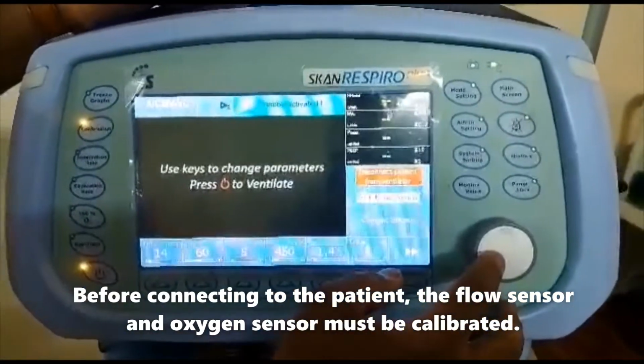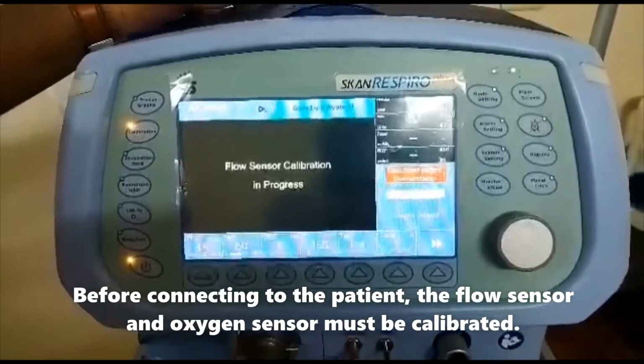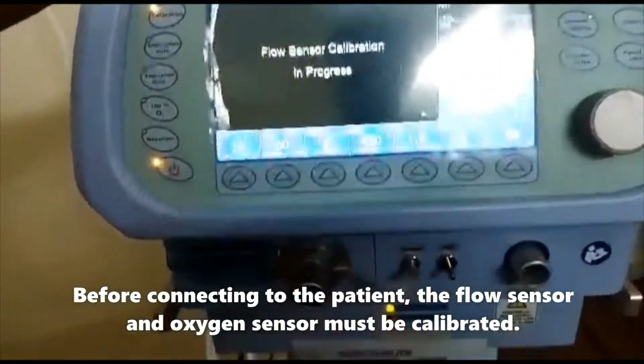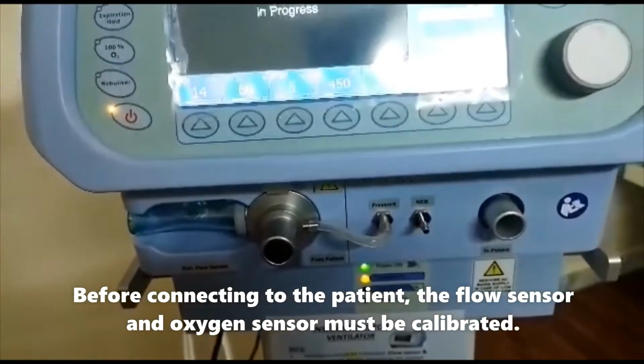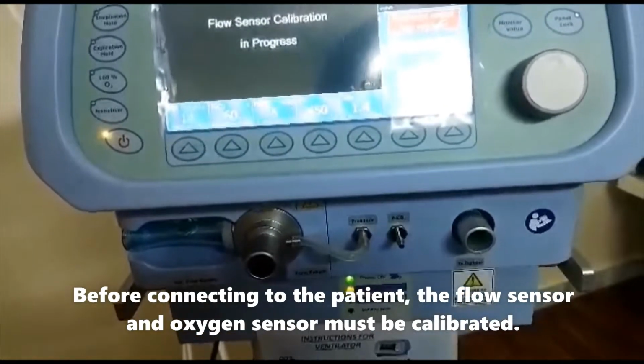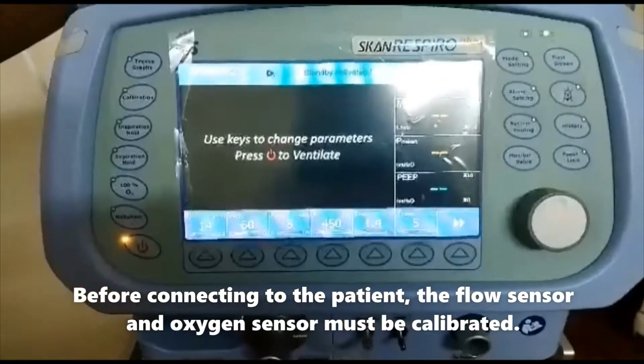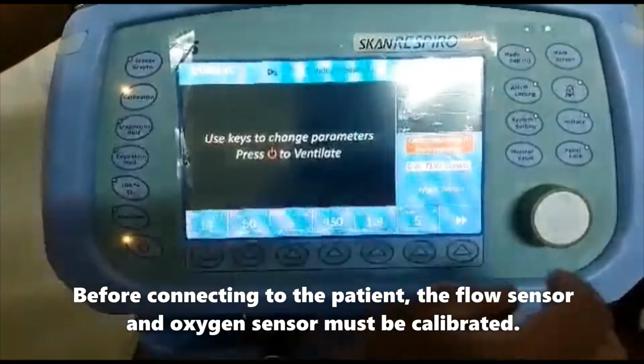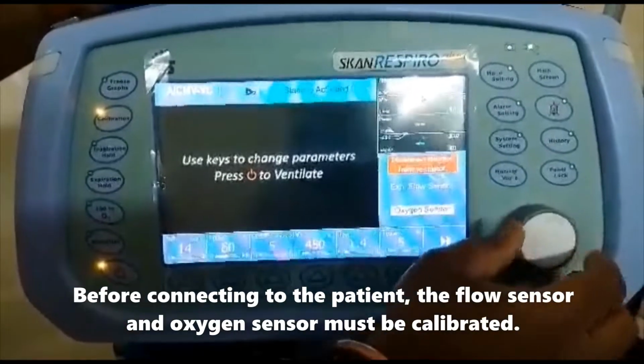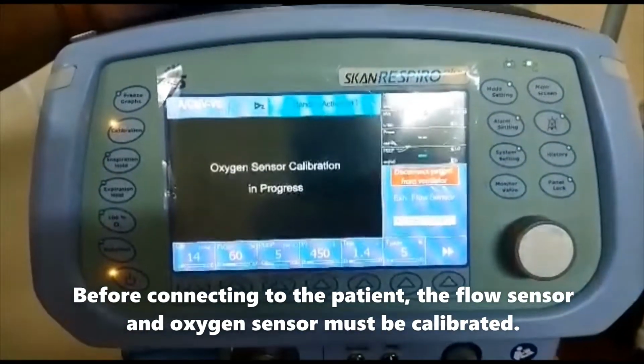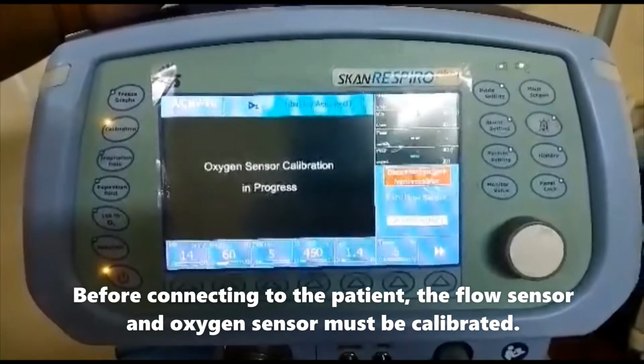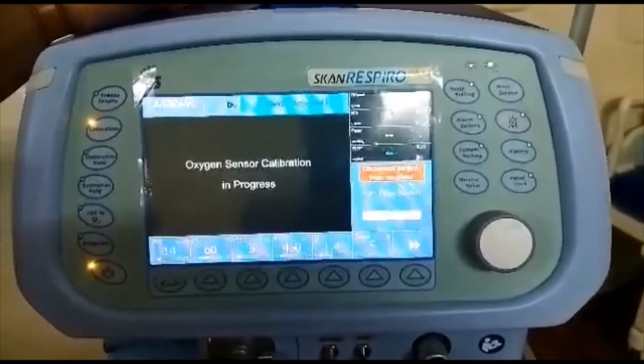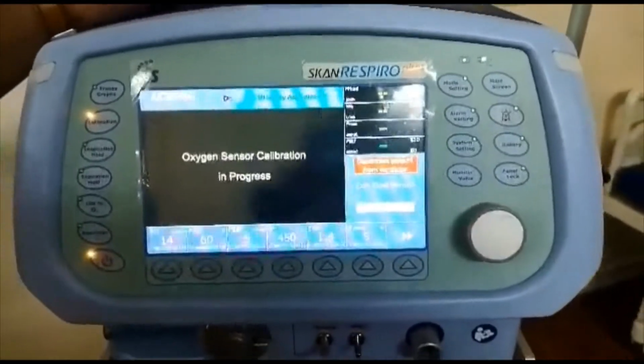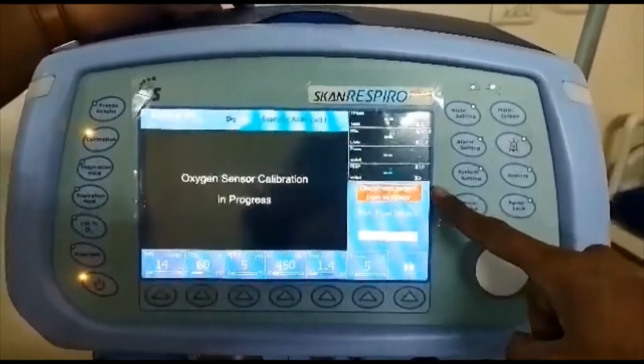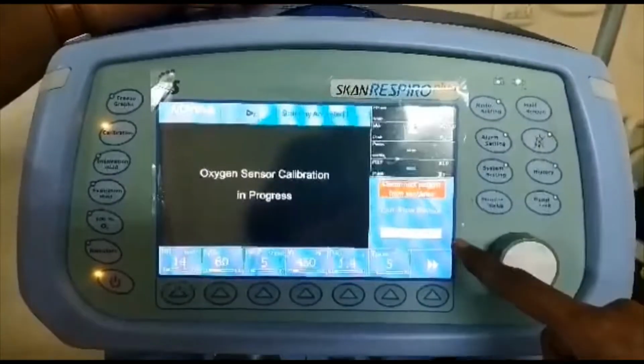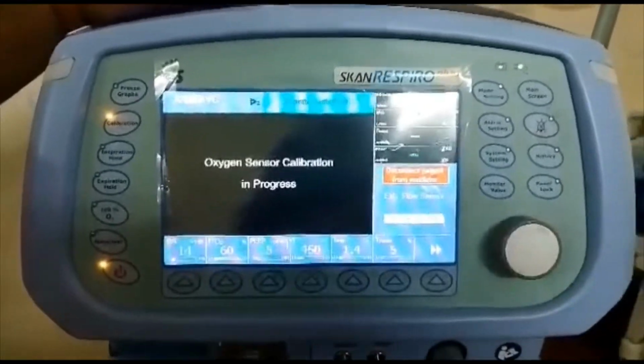So now flow sensor calibration. We should not connect any circuit to the patient. Once it is successful, then the oxygen sensor has to be calibrated. It takes hardly 30 seconds. It shows to disconnect the patient from the ventilator. So the flow sensor has been calibrated. Now the oxygen sensor calibration is going on.